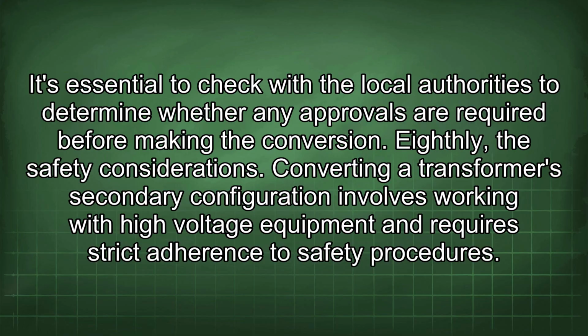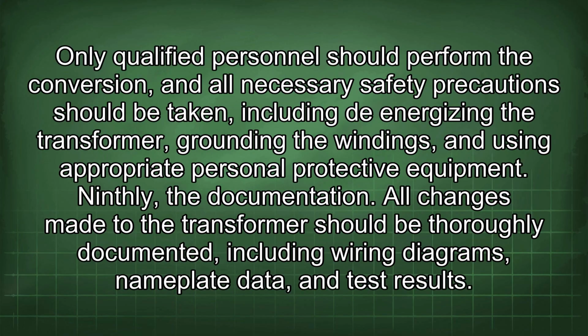Eighthly, the safety considerations. Converting a transformer's secondary configuration involves working with high-voltage equipment and requires strict adherence to safety procedures. Only qualified personnel should perform the conversion, and all necessary safety precautions should be taken, including de-energizing the transformer, grounding the windings, and using appropriate personal protective equipment.